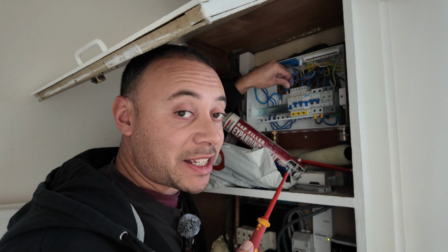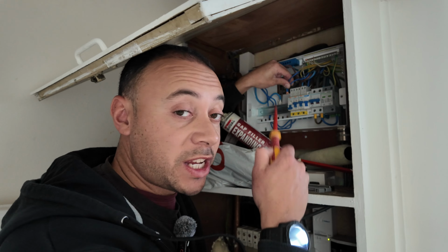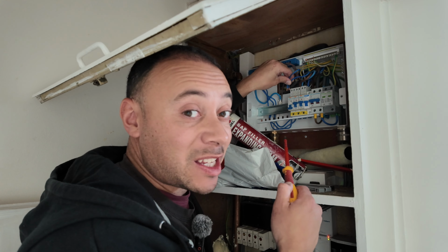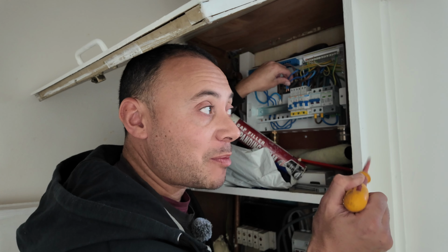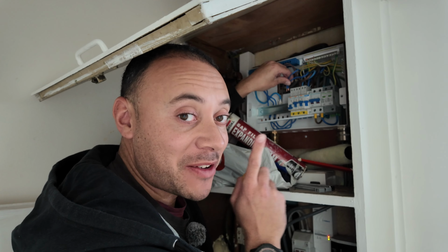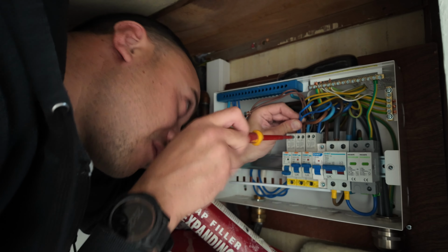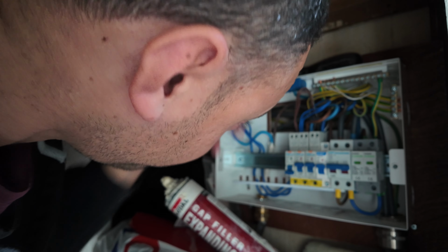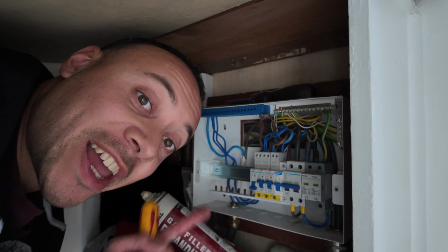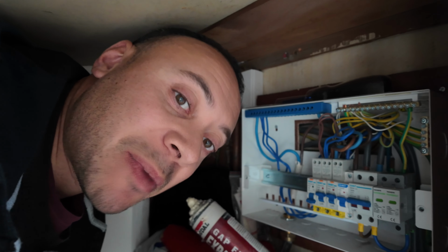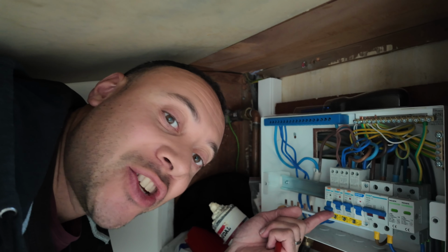Okay, so I'm going to put the circuit back together. I just did a cheeky earth continuity, got perfect continuity on the ring circuit. So I'm going to now get this back together, and I'm going to try and plug in that toaster. Let's see if it trips. It'd be very interesting. Okay, cables back in. I've tightened them up, and I gave them a tug test to make sure that they were actually clamped under the terminal properly. It's time to energize the circuit.